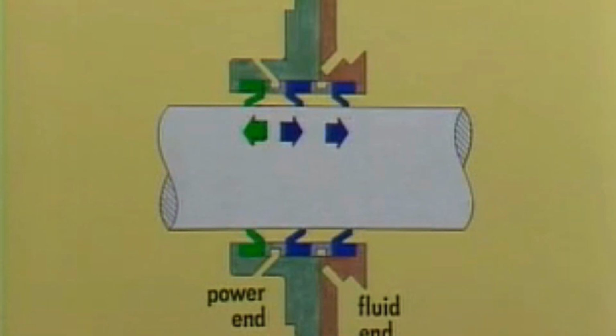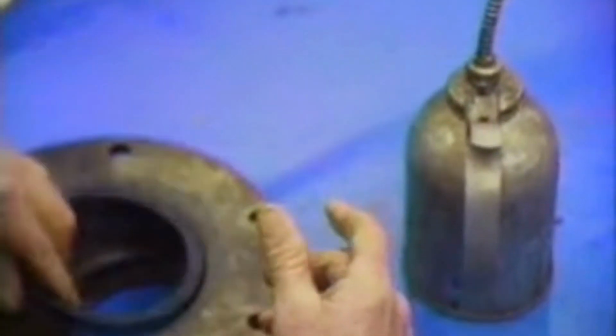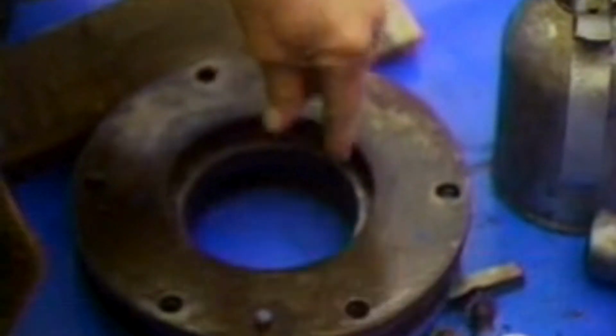The first ring's lip should face the power end of the pump to keep the oil in the crankcase and out of the cradle. The next 2 rings should have their lips toward the fluid end to keep mud and water out of the gear end of the pump. Oil the lantern rings and wiper rings before installing. Place a wiper ring, lantern ring, and then another wiper ring in the diaphragm housing. The lips of the 2 wipers should face away from each other, toward the outside of the housing.